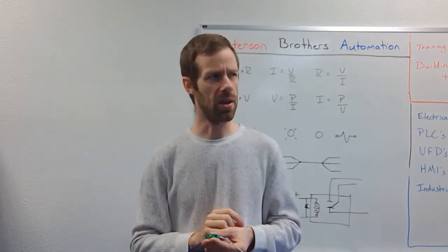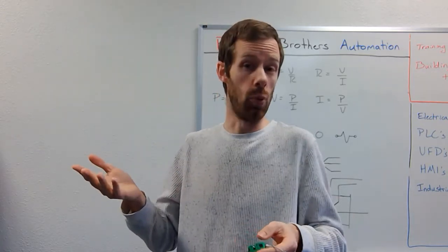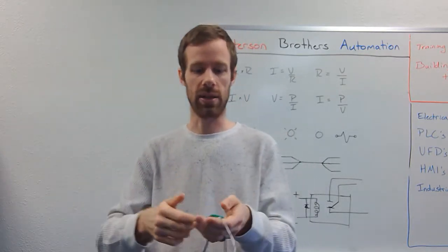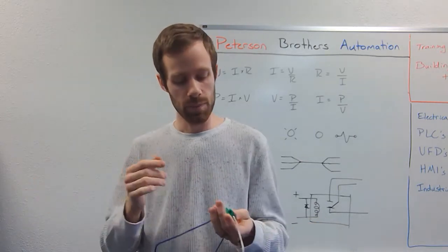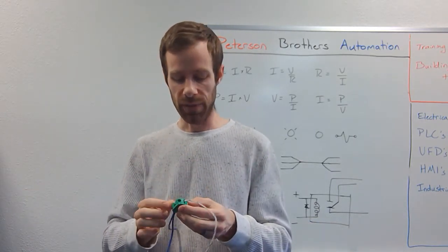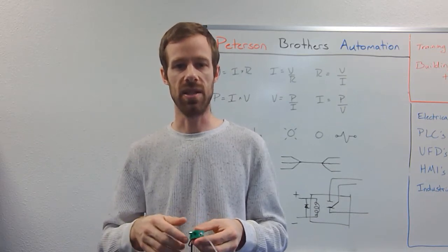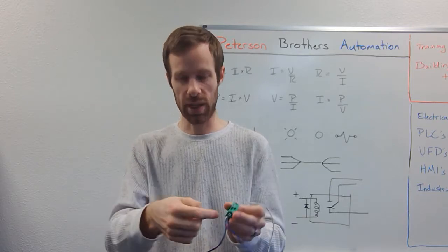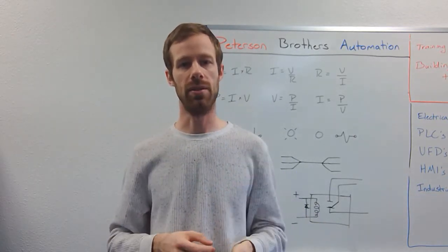Two main reasons why I don't really like that method. While it technically works, because all three of those wires, just like the wire nut making a connection, are going to be connected together, it's all right, but two problems. The first one is, what if I needed a third wire connected there instead of just two? There's really not much I can do. I cannot cram another third wire underneath there. I simply don't have room to get a third wire under there.